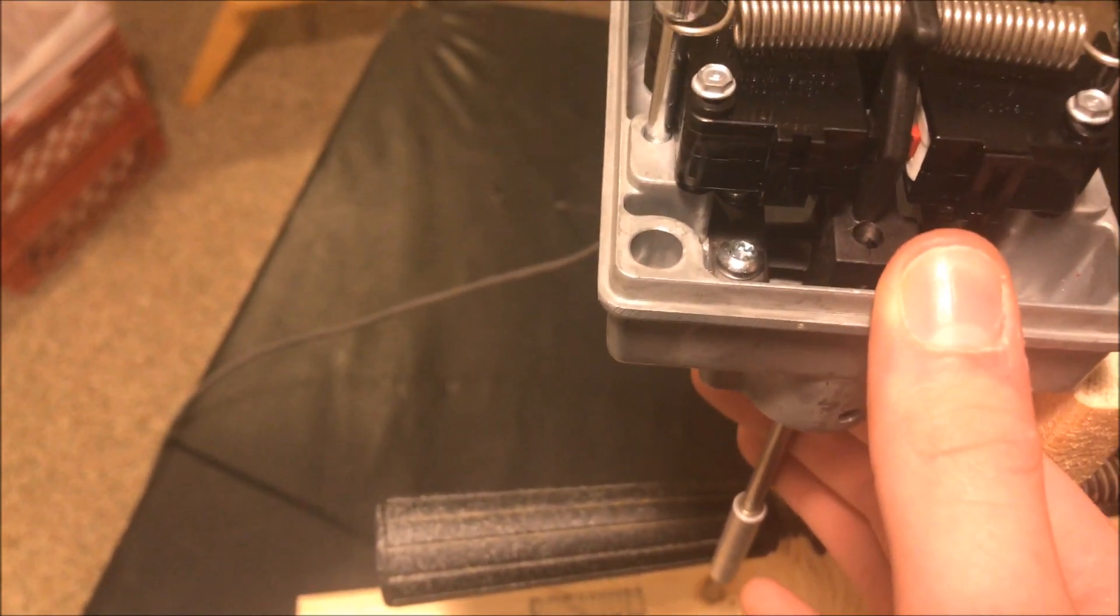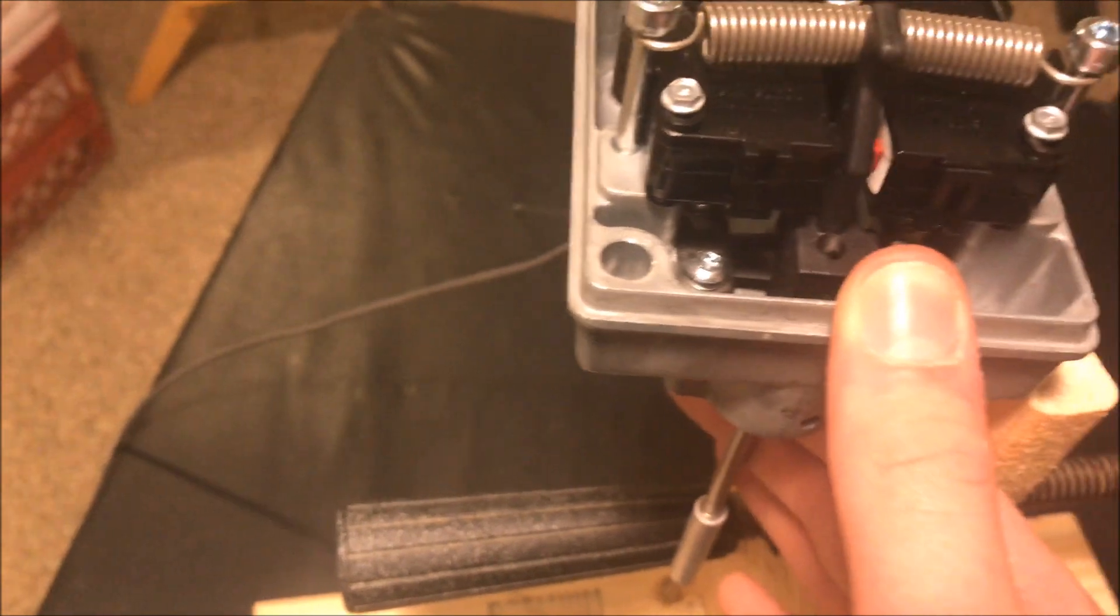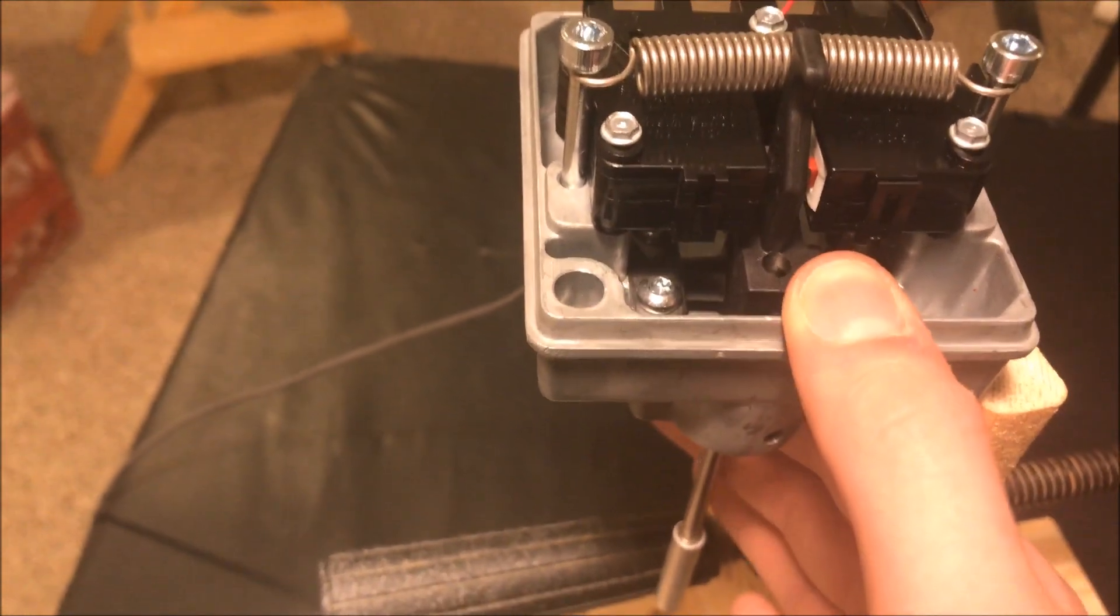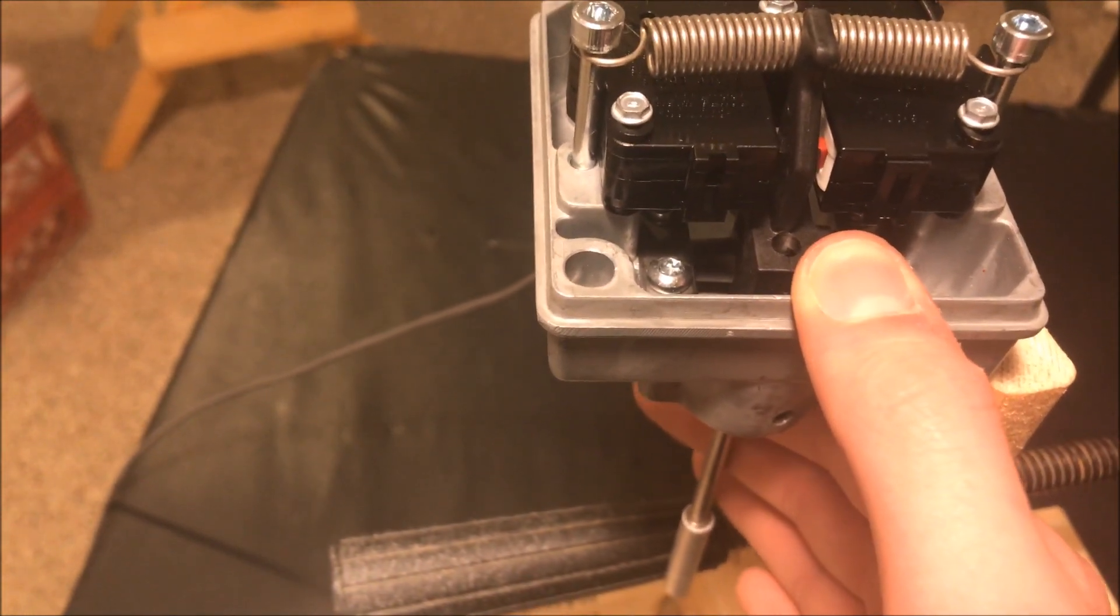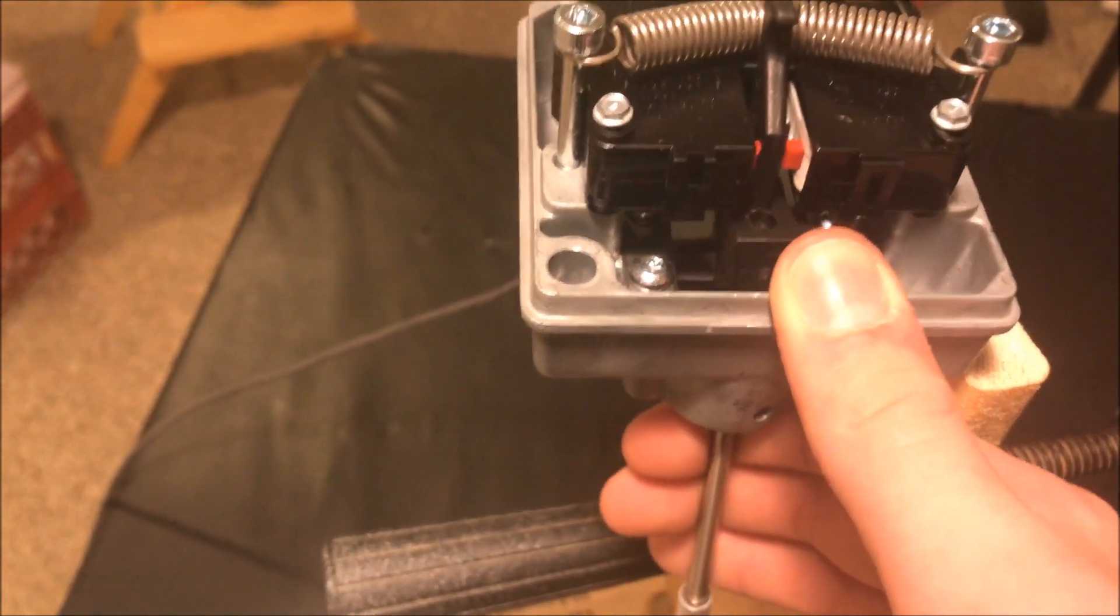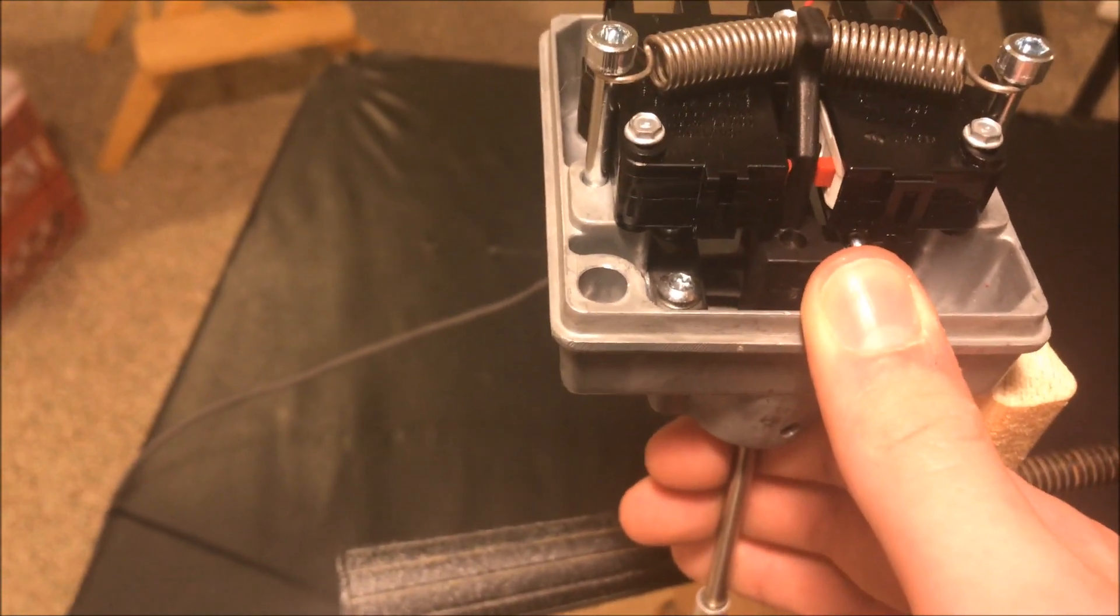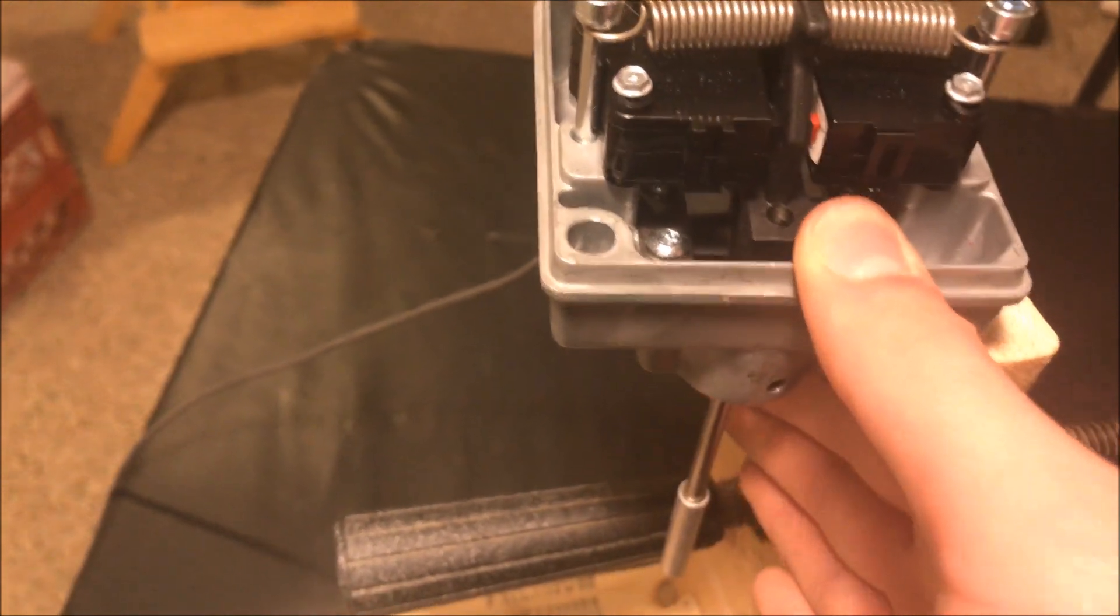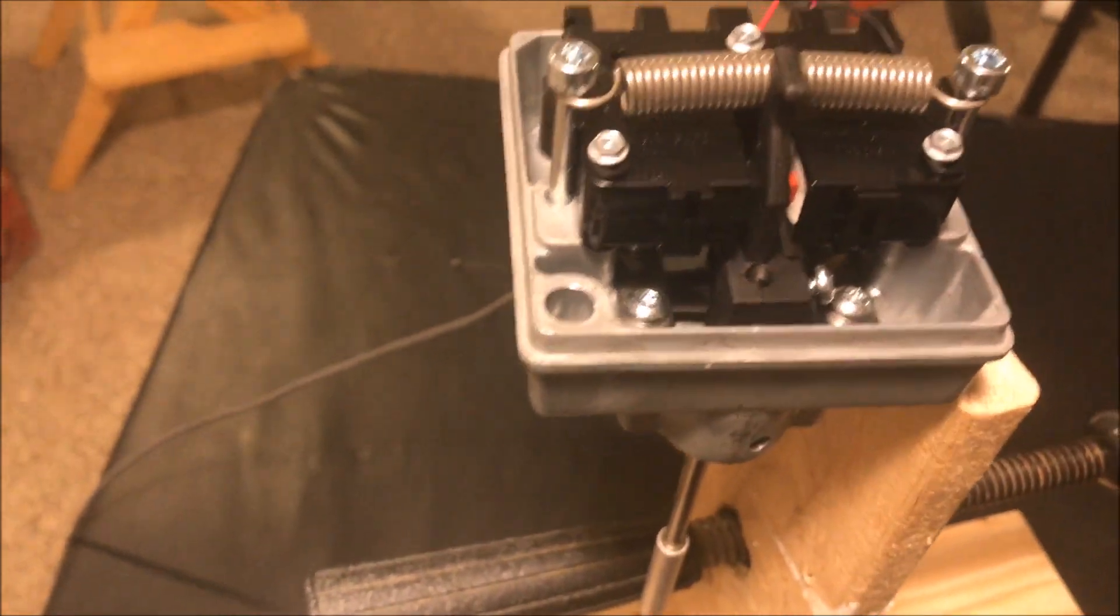That is what actually triggers the supervisory. As you can hear the panel beeping. When the switches are pushed in, that is normal condition. When the switches are pushed out, that is a supervisory condition.